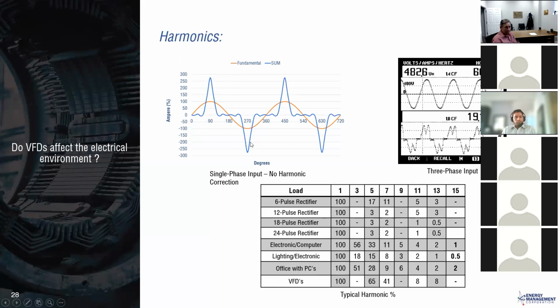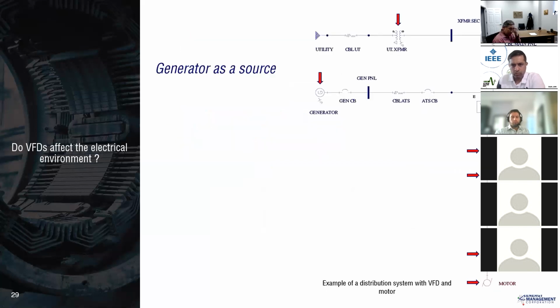These are the typical harmonic percentages that you see in various applications like 6 pulse, 12 pulse, 18 pulse, 24 pulse, electronic lighting, PCs and VFDs. You can see that PCs are the largest contributors of harmonics, but when it comes to VFDs, this is what we typically see. In most applications, VFDs come with an input reactor, which is common, and we don't see such bad numbers as displayed here. So this is typical.